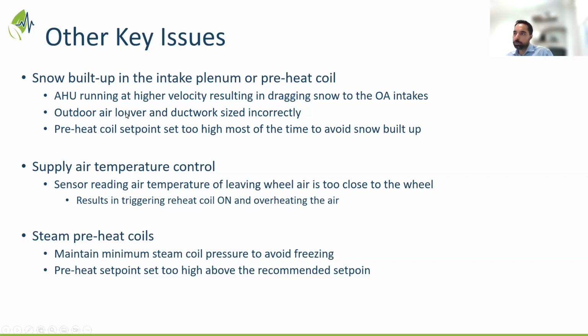Again, it's a combination of a few things. One is AHUs running at peak capacity. The second is the design of the outside air louvers and the ductwork. All of this is not only giving trouble to the facility operations team, because they're trying their best to run these systems, but they're stuck with this issue where their systems are performing undersized in terms of the amount of air that needs to be delivered. So they have to run those systems at a higher speed and higher airflow. And then the outside air louver and the ductwork design isn't aligned to make sure that you don't get that snow built up in those coils.